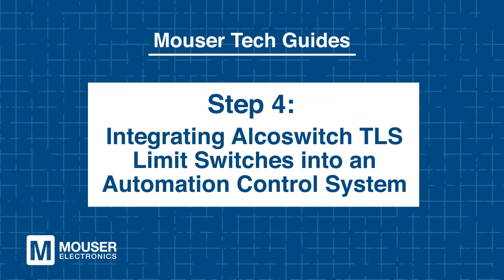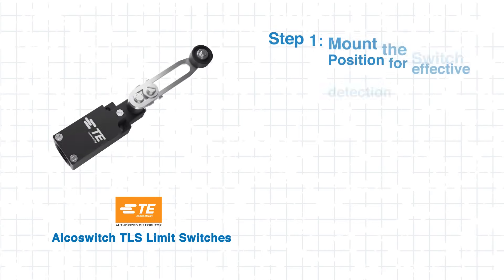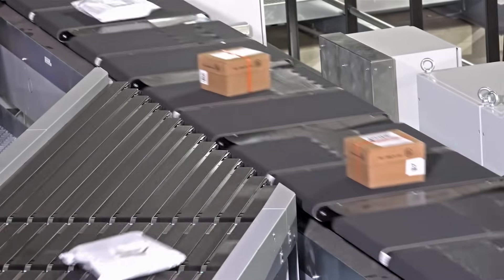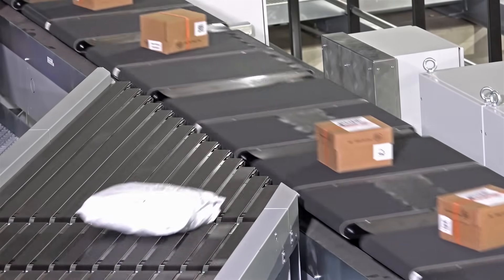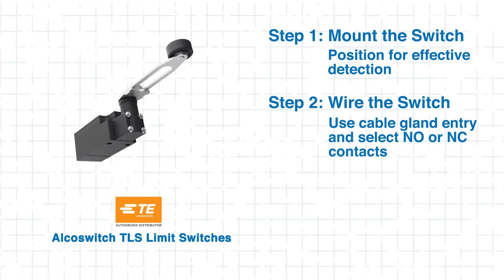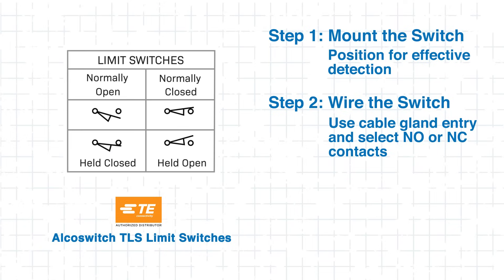Step 4: Integrating AlcoSwitch TLS Limit Switches into an Automation Control System. Integrating a TLS Limit Switch into your manufacturing line gives it precise control and optimal safety. First, mount the limit switch in a location where it can effectively detect the target object or position — for example, on a conveyor system to detect material presence at specific points. Next, wire the switch using the cable gland entry for easy integration into your control system. Choose between normally open or normally closed contacts based on your application. NC contacts are recommended for safety, as they break the circuit when the switch is activated.